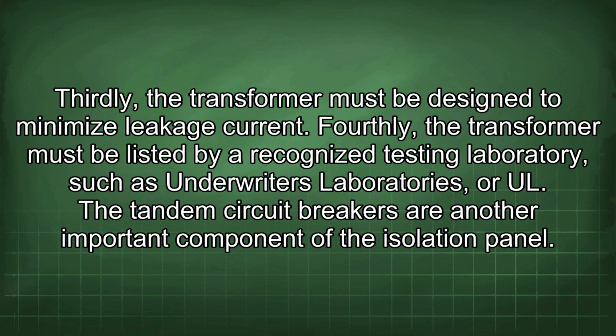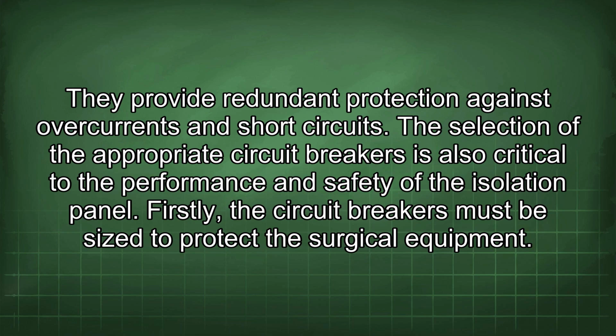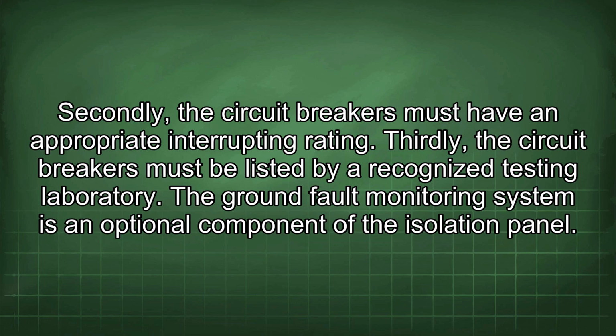The tandem circuit breakers are another important component of the isolation panel. They provide redundant protection against overcurrents and short circuits. The selection of the appropriate circuit breakers is also critical to the performance and safety of the isolation panel. Firstly, the circuit breakers must be sized to protect the surgical equipment. Secondly, the circuit breakers must have an appropriate interrupting rating.